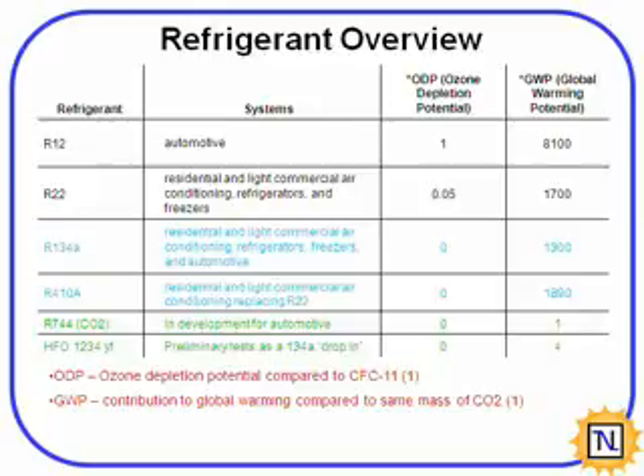So as things progress, R134A and 410A are coming in to replace these. So you can see there's no longer any ozone depletion from these refrigerants, but still significant global warming potential. And that's the next thing that needs to get knocked down. And we're phasing into some new refrigerants, one of which is CO2, being developed mainly for the automotive systems, so that'll be replacing 134A. And then there's a new refrigerant that's not quite out yet, 1234YF, and it's meant as a drop-in for the 134A system. The CO2 is a unique fluid and it's a high-pressure refrigerant, so additional design and consideration needs to go into this to make it feasible as a refrigerant.